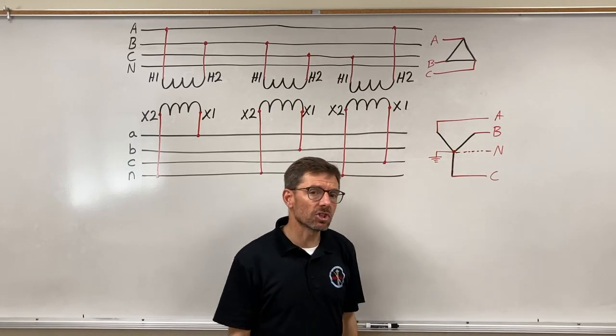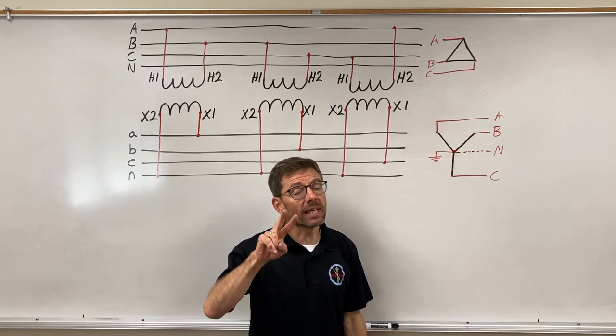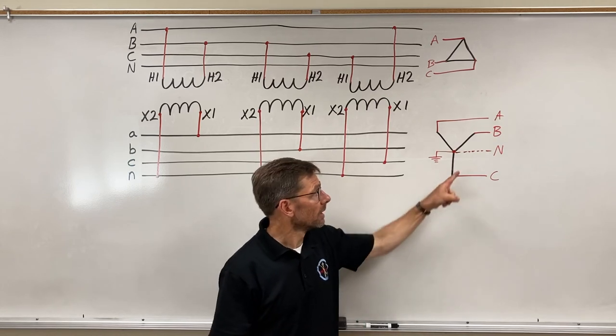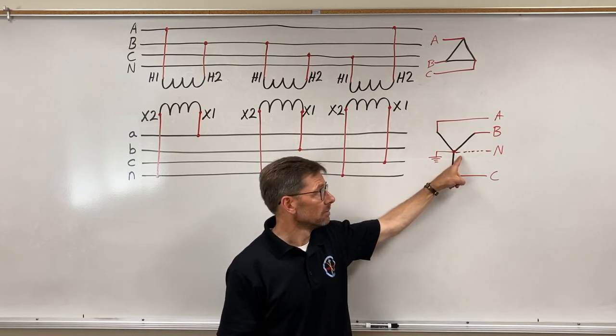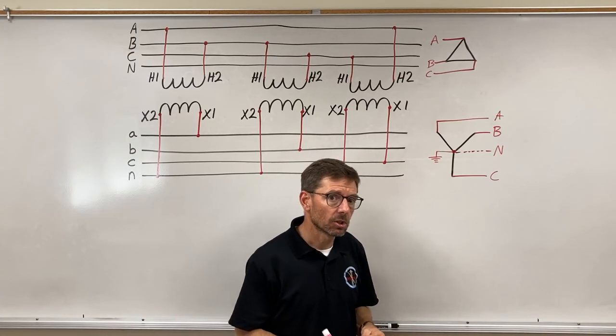Generally speaking, only in two places. In a transformer, we call that a separately derived system. In the code, in a separately derived system, the ground and the neutral can meet.